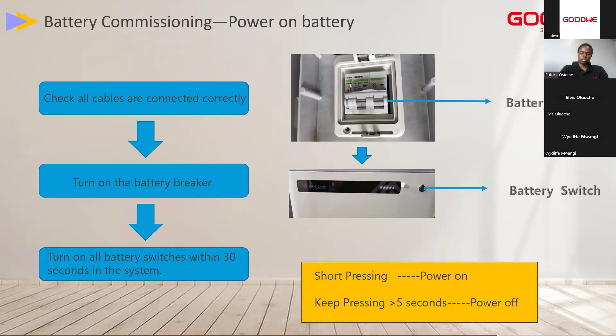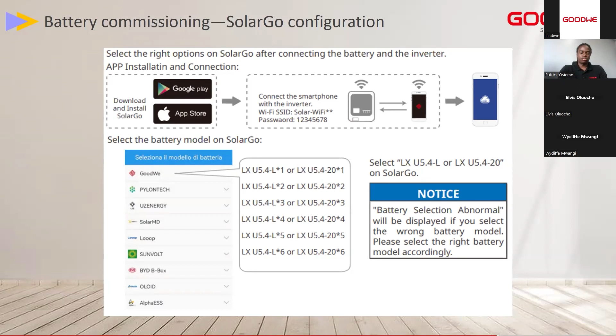Commissioning is easy. GoodWe has its own commissioning software called SolarGo. Through SolarGo, you actually commission the battery through the inverter itself - it's an all-in-one, simple, fully integrated commissioning style, accessing the battery through the inverter with no need for two separate softwares. During commissioning of the inverter, one step is choosing your battery - select the Lynx battery, choose the number of pieces, complete the steps, and the battery is commissioned.